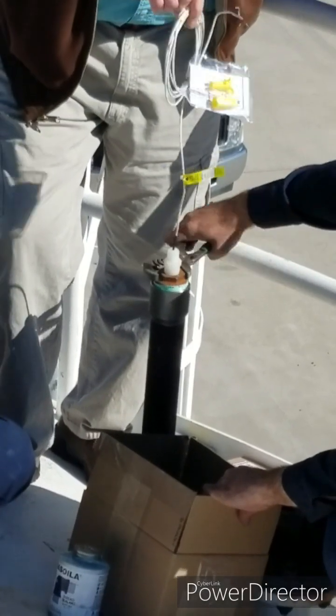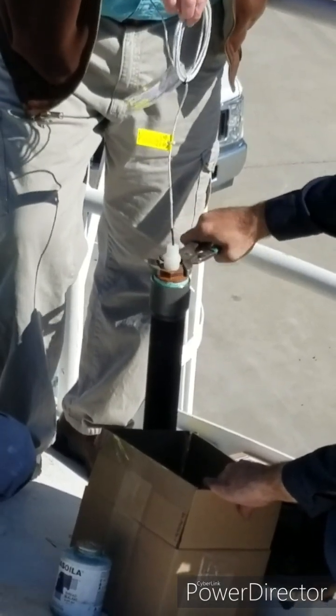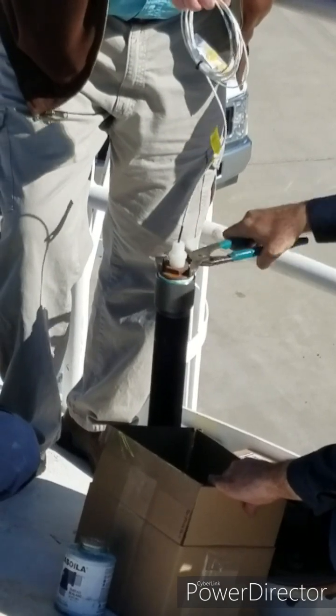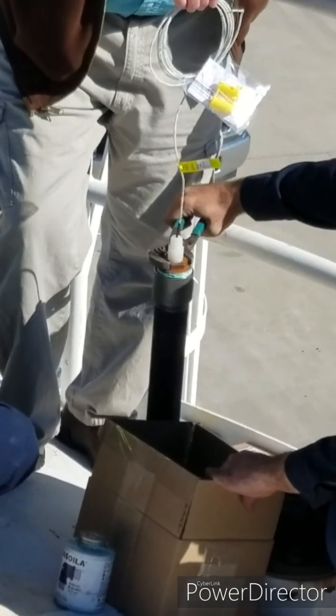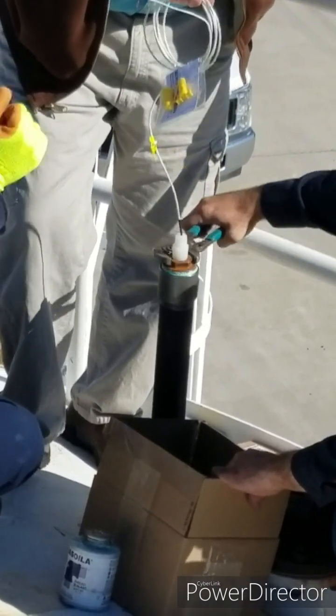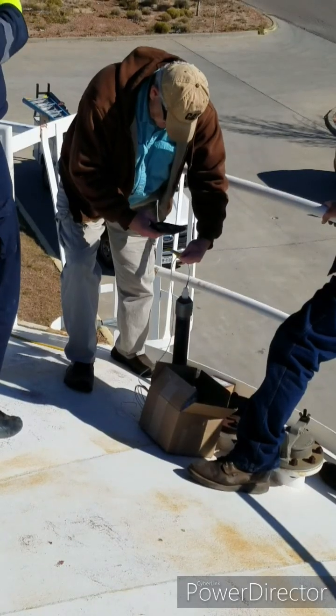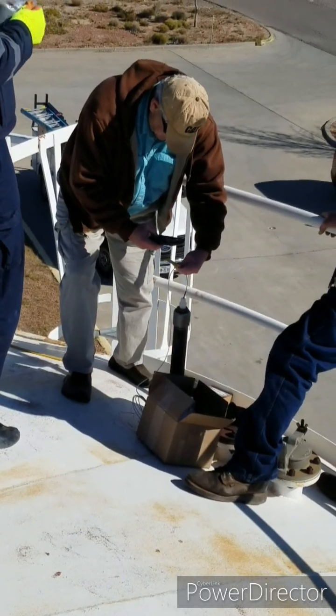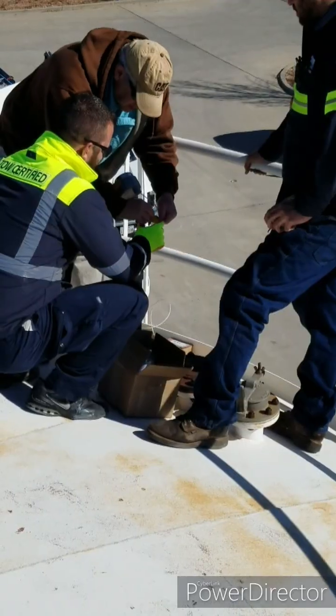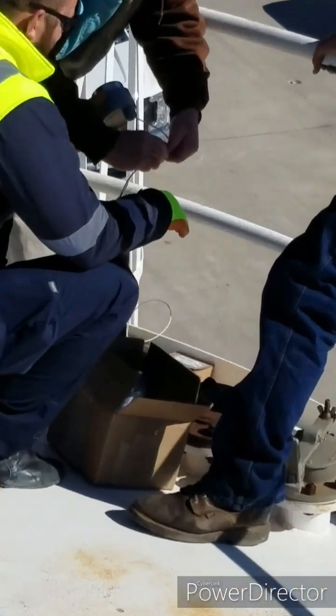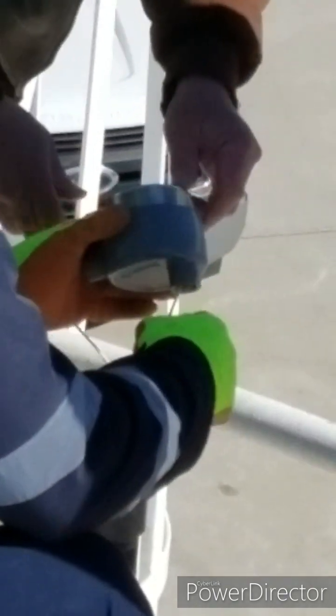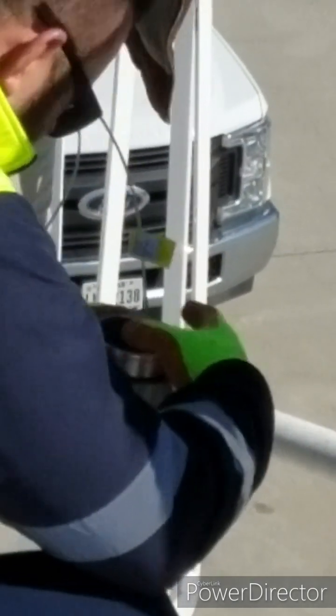The probe tag should remain on the probe wire, and it is a good idea to make note of the probe tag if you haven't already done so, as this is needed when programming the TMS console it connects to. You are now ready to install the housing onto the top of the probe. Be sure not to bend or strain the probe when installing the conduit and vapor seal fitting onto the housing.